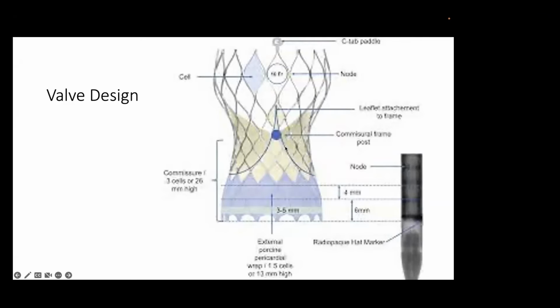The other things to understand are that the skirt goes up to about 13 millimeters all the way around. The commissures go up much higher. I believe they go up to 26 millimeters, and these gaps between the wire mesh are about 16 French. If you need to get in through the, sorry, not 16, I think 10 French or 12 French. But you should have an understanding. These measurements are available online to look at, but ideally you need to understand the nodes and the distance. The first two nodes are 6 millimeters apart, then each one after that is 4 millimeters apart, and that helps you decide your implant depth.